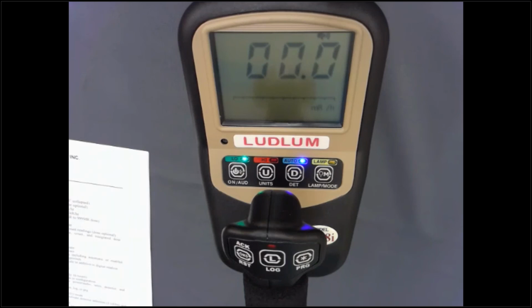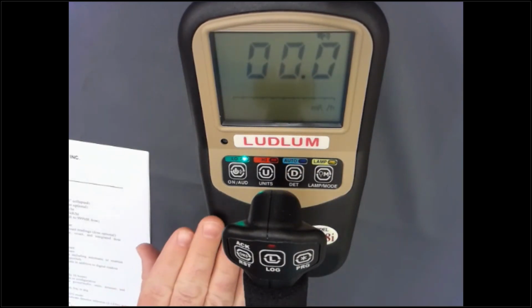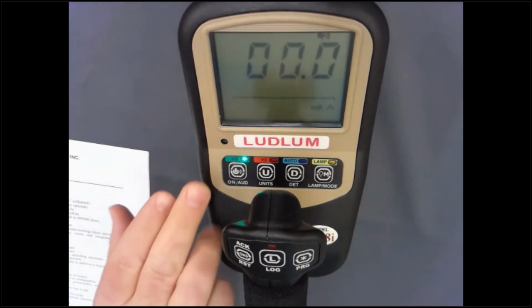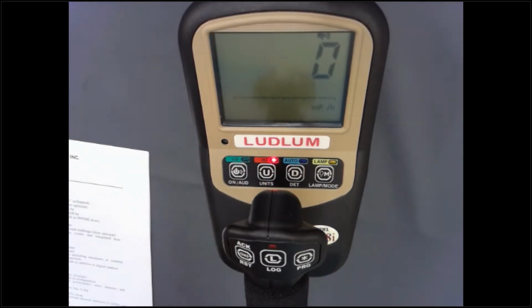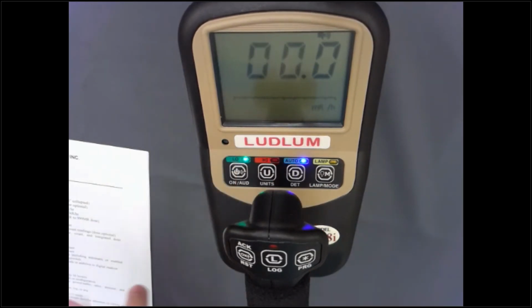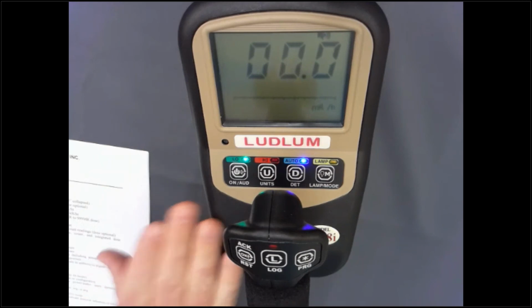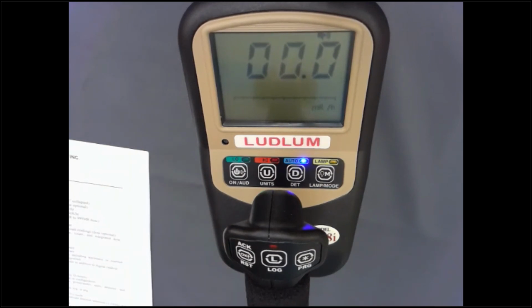The instrument is set up so that the low range external detector, as well as the internal detector, is configured to operate from 0 to 2 R per hour, and the high range being 0 to 1,000 R per hour. And it will physically latch at that point if you're looking at an individual detector. So at this point, it will not go higher than 2 R per hour because we are latched into the low detector mode. And if we go to the high detector mode, it will go to 1,000 R per hour. But what happens in auto ranging is when it reaches the 2 R per hour maximum that we've set for the low detector, it'll automatically range over to the high range detector and continue from there.